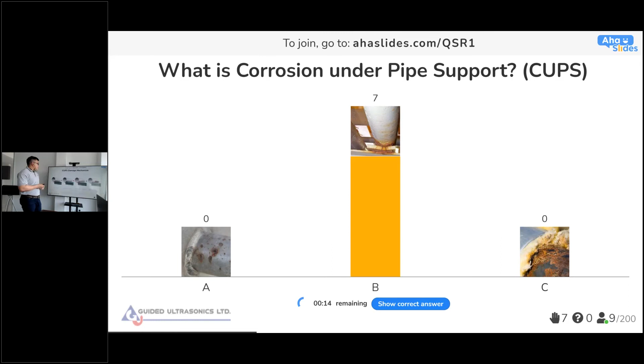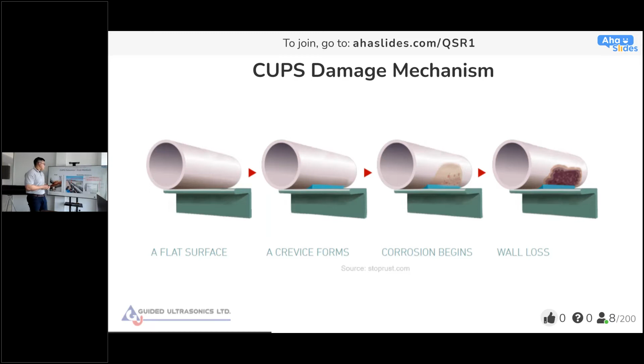Just a bit of insight on CUPS: it's what happens when you have water trapped in the crevice between the curved surface of the pipe and typically the flat surface of a support. The water trapped there could lead to damage of your pipe coating, which eventually leads to corrosion or metal loss in the pipe wall.